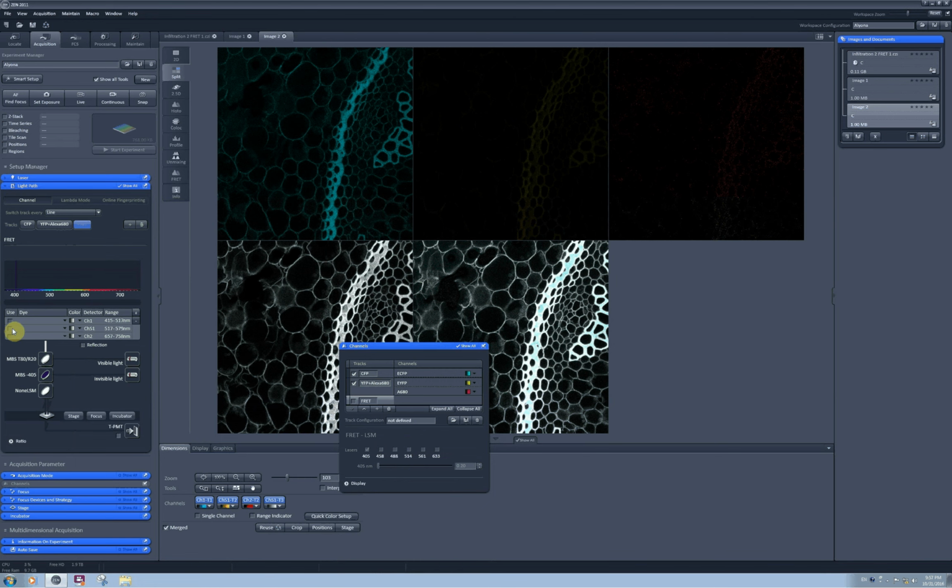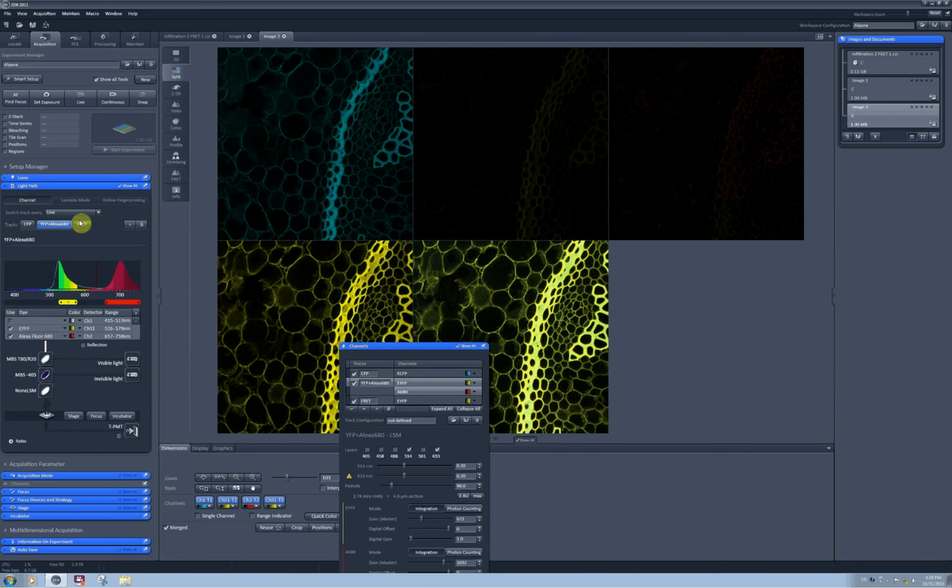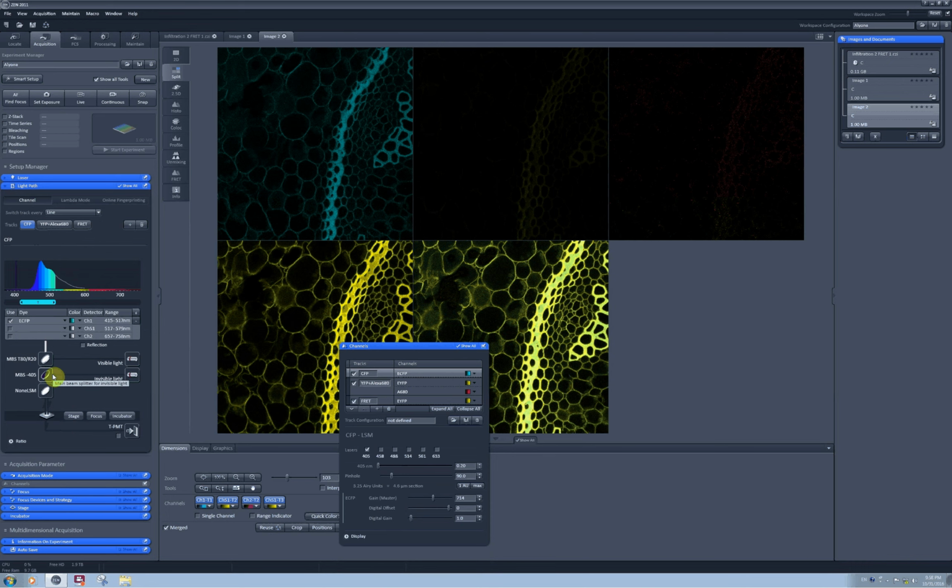So I go here. And it automatically matches the detection range in track 2 and track 3. Every line switch between the tracks is very, very fast, and confocal hardware cannot move fast enough. The main beam splitters, it cannot adjust the pinhole fast enough, and it cannot also move the prisms and sliders fast enough. The settings of the MBS, prisms and sliders position, and pinhole have to be compatible for all three tracks.